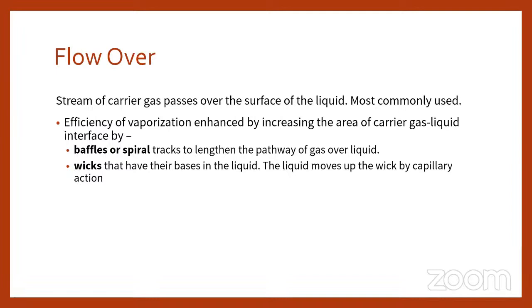It is basically the same principle as when we light a diya during lamp lighting ceremonies. Basically, the tip of the wick is in the air and the bottom of the wick is dipped in the solution. So the liquid anesthetic agent that we are using to anesthetize the patient, which is present in the reservoir, comes to the tip of the wick through capillary action. So whenever the gas flows through the wicks with an increased surface area, more vapor will be mixed with the fresh gas and a higher concentration will be delivered to the patient.